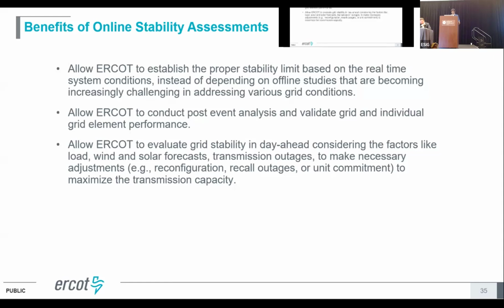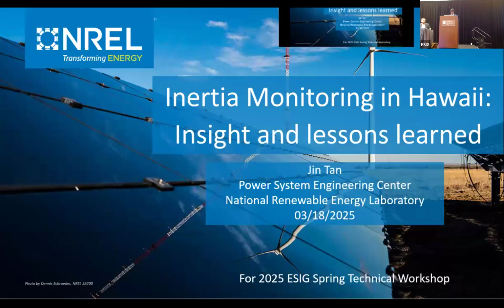The main advantage is that since we can do these assessments in real time, or run the same assessments in our studies, we can see how it's going to change a few hours from now, or at midnight, or next day, or during peak load the next day. We can see how the stability limits will look based on current forecasted conditions, because for the next 24 to 48 hours we have a very good renewable forecast, so we know exactly what wind and solar will do. We can use that forecasted information to come up with limits for the next 24 hours, which can be used in our day-ahead and reliable unit commitment tools to bring more generation online as needed. That's my last slide.